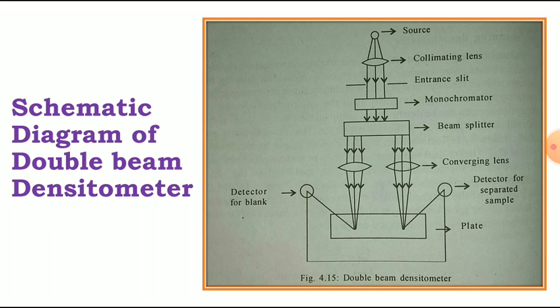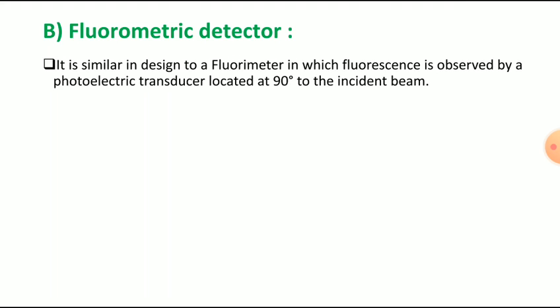Now the second part from detection and visualization is the fluorometric detector, which we are going to see next. This type of detector is used for detection of separated components on the TLC plate. It is similar in design to a fluorimeter, in which fluorescence is observed by a photoelectric transducer located at 90 degrees to the incident beam. A vapor lamp or xenon lamp is used as the radiation source.